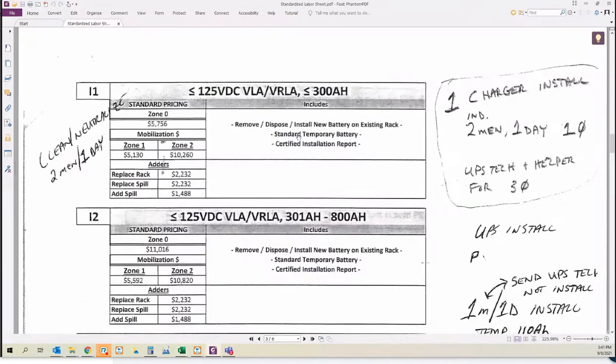On the existing rack, our standard temporary battery is 110 amp hours, 120 volts. You can call it 125 or whatever you want, but it's a 120 volt setup with 110 amp hours as our standard backup.